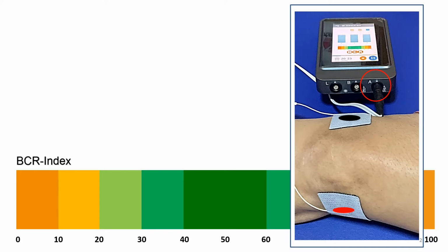So once the treatment starts working, the treatment runs in this pathway. It comes through one electrode, it goes through the body to find the other opposite electrode, and then it goes back to the machine, and that's how the reading happens. And BCR being bipolar, the current runs in both directions. So from here you can know that it's important to apply the electrodes in such a way that the treatment passes through the target area that you want to treat. This is the area, the dotted area. This is where the treatment is happening, and also the measurements are happening.